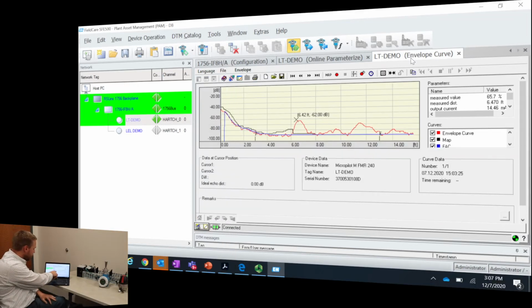The black line I was talking about before has now pulled in also. You can see that here. A lot of our troubleshooting is all done via the black line. You can't really change the red line. The red line always tells you what the radar is seeing. The black line allows you to tell the radar to ignore false disturbances. Let's say you had a red hump up toward the top here and your device was reading 90% full, but again your tank's only 50% full. We could manipulate this black line to map out that false echo toward the top of the tank.